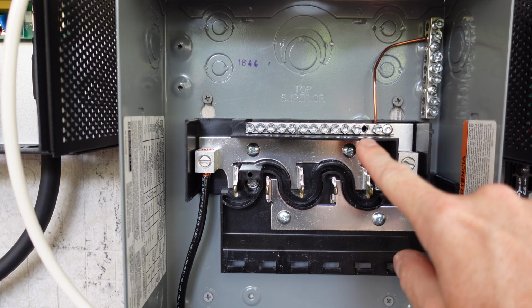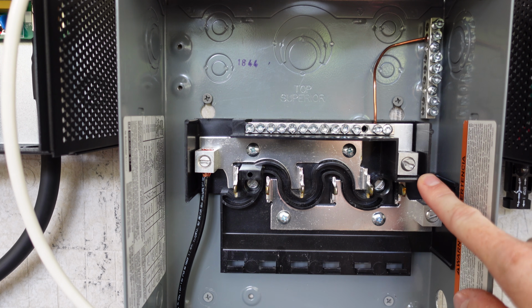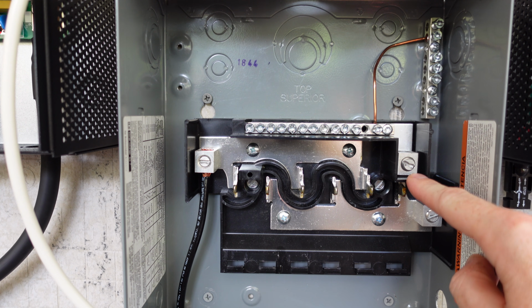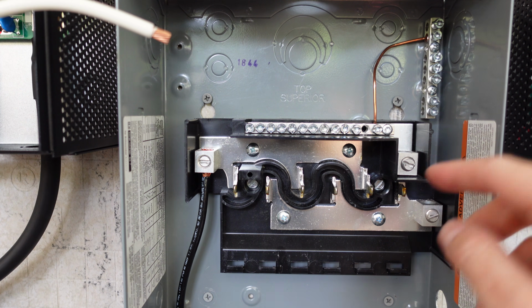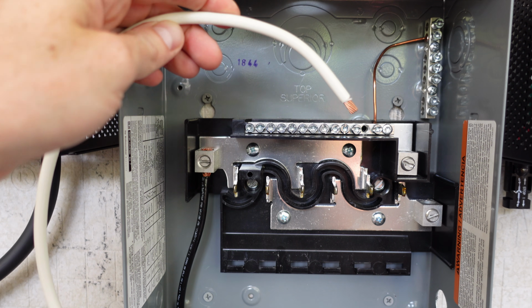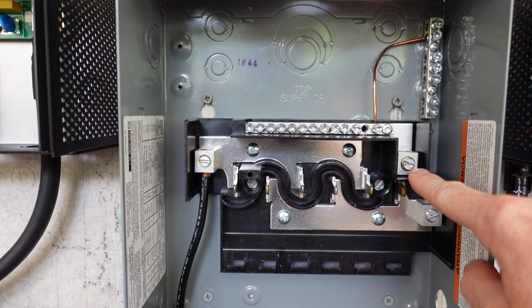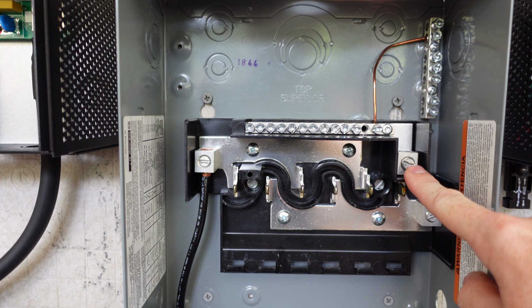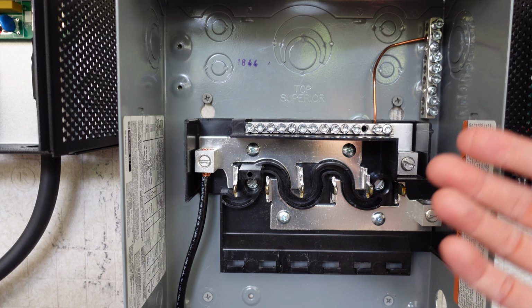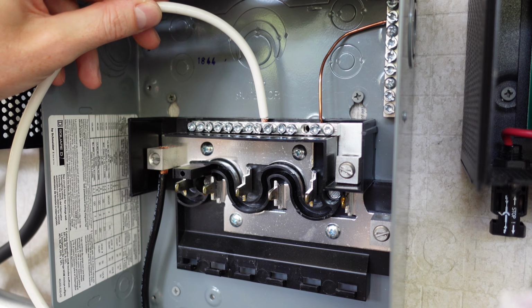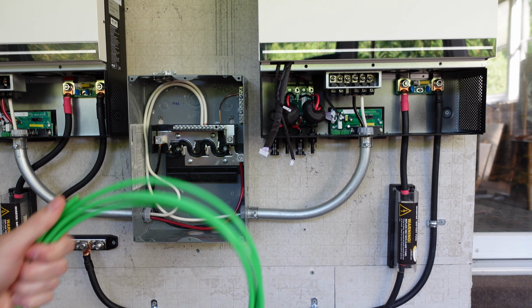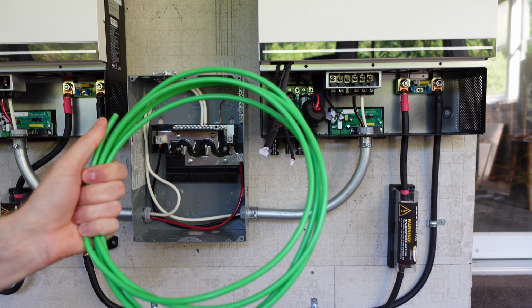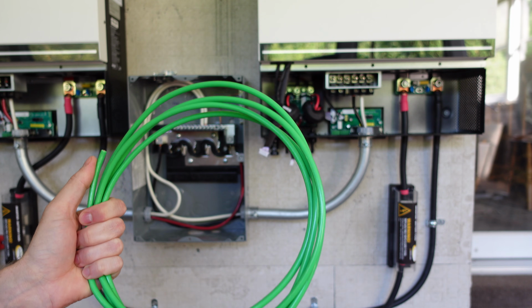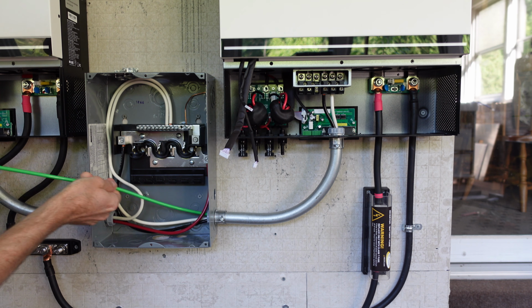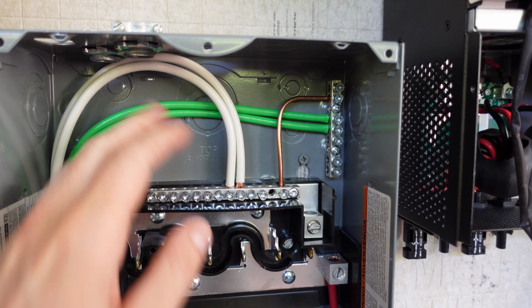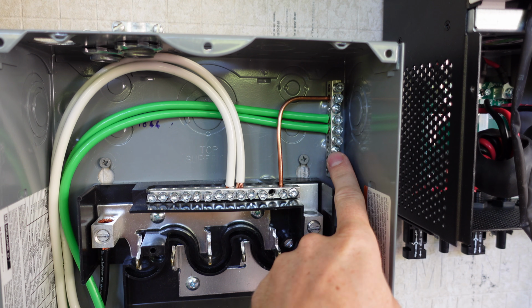Alright, so this neutral bar on the top here does have a main lug where you would typically connect the main neutral. However, since we have two inverters, we're going to have two neutral wires coming in, and you cannot put two wires on one of these main lugs. I mean, technically you can, but I'm pretty sure that's against code. So for the ground conductor, I'll be using this number 6 THHN. Both of these ground conductors are going over to the separate ground bar here on the right.